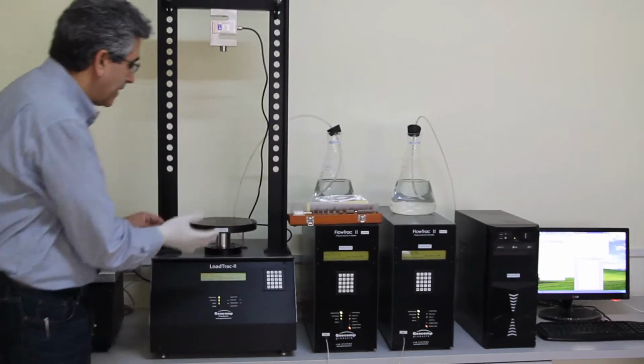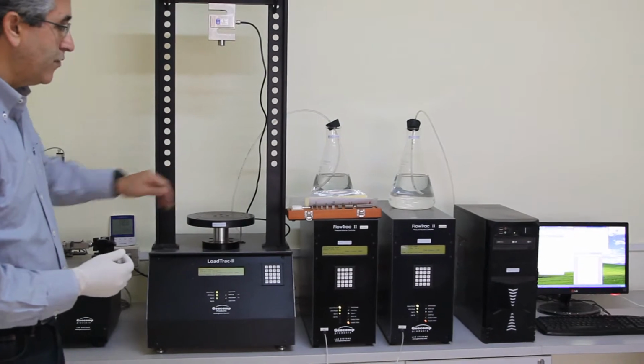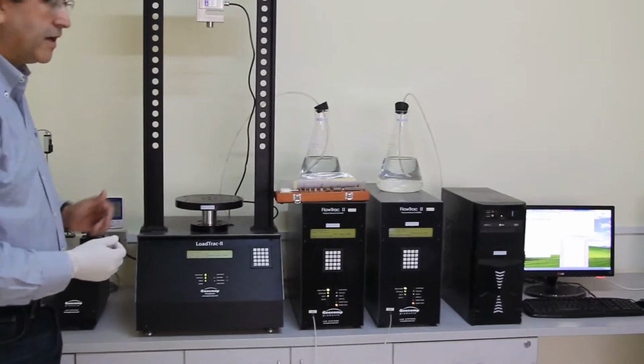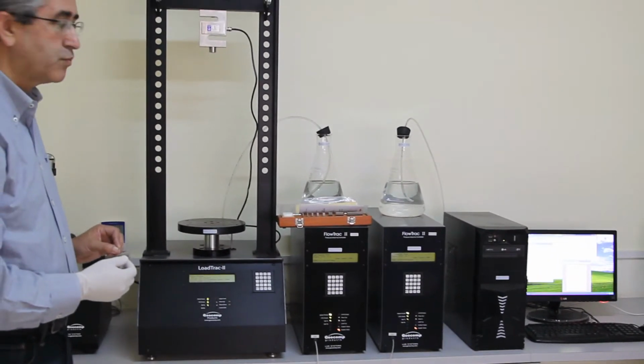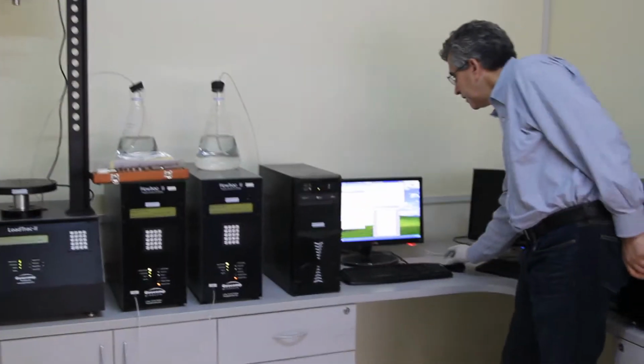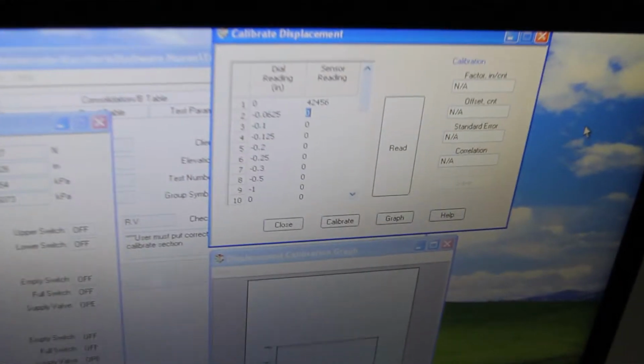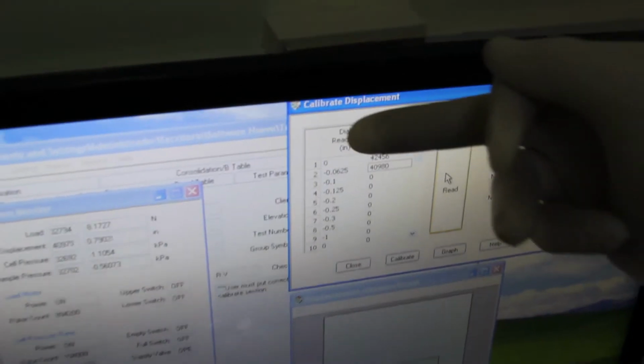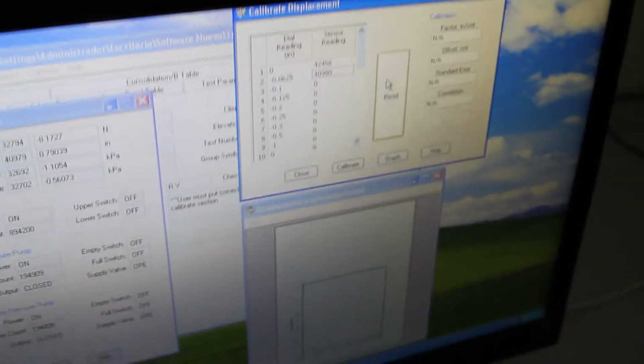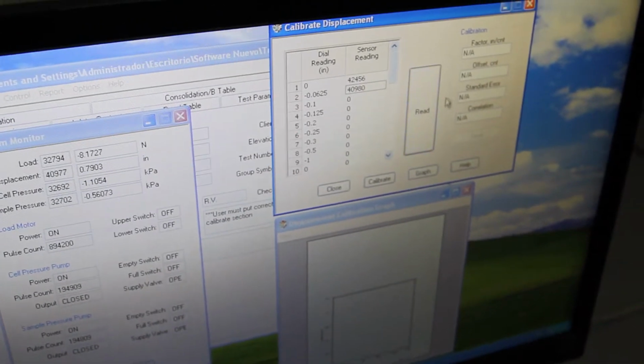So now the displacement sensor has moved down by the amount of the thickness of the gauge block, which is 0.0625. Now I'm going to go to the software and look at my dial reading, which is 0.0625 inches. That corresponds to my first gauge block. And I'm going to do read. So now it's going to read the displacement from what was 0, which was our reference. You notice here that the numbers are negative, because we are doing the calibration in descending order, so we can get a calibration factor that is positive.